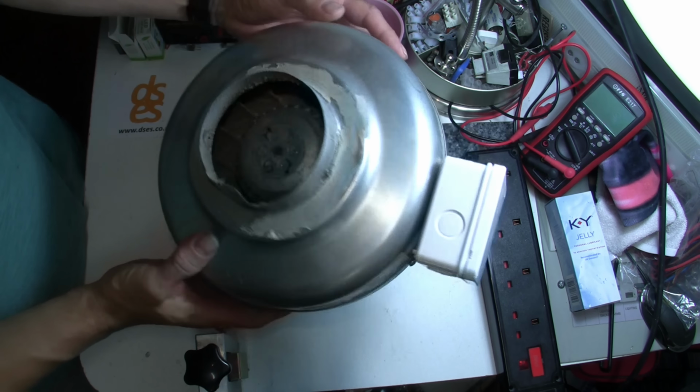Cutting neutral means an apparent dead fan remains live, and its neutral is now floating at 230 volts, waiting to catch out the unwary. Here's what I don't like about this thing. Had I used it on site as I intended, then as the designer and installer of a fan circuit employing this product, would I have fallen foul of BS 7671?